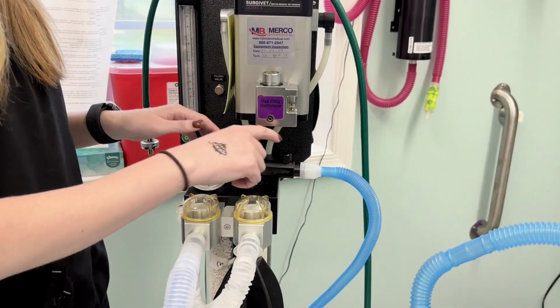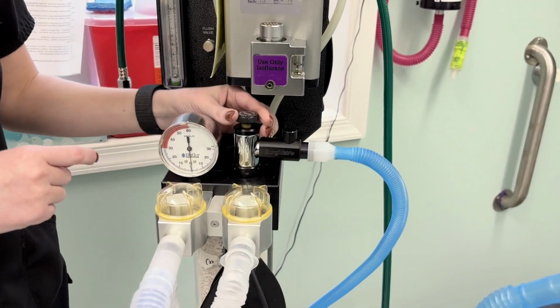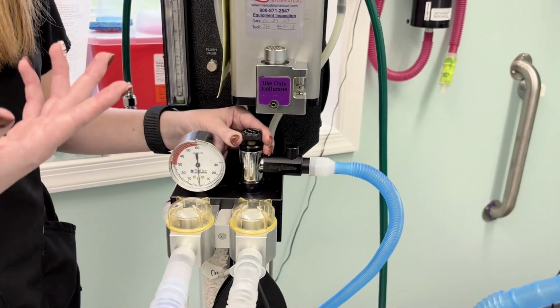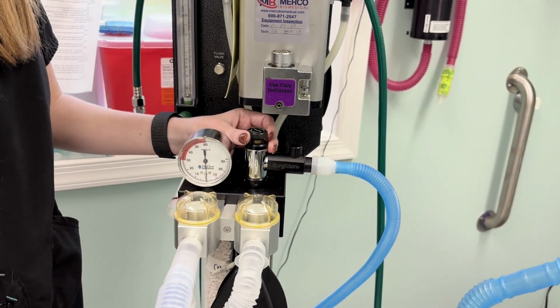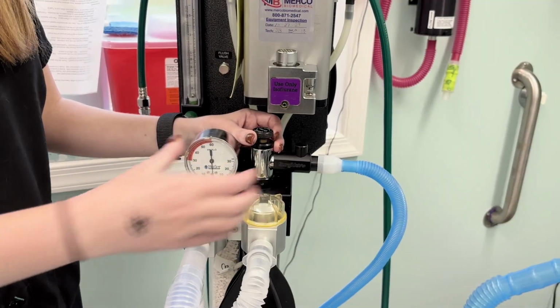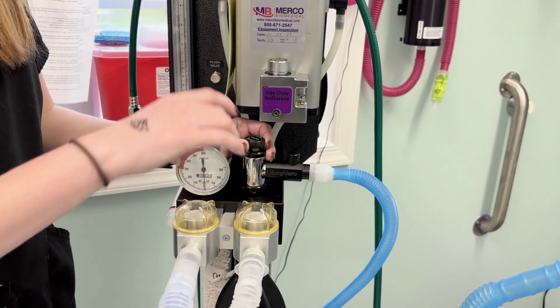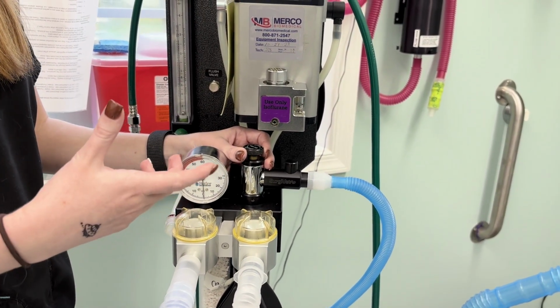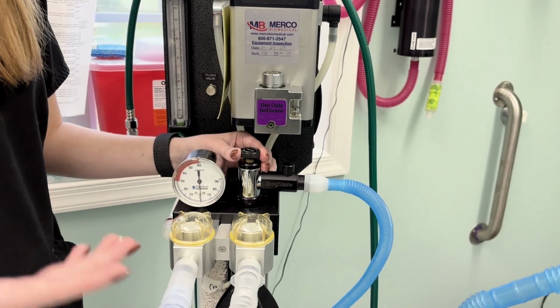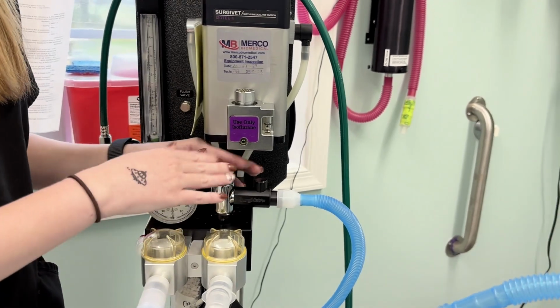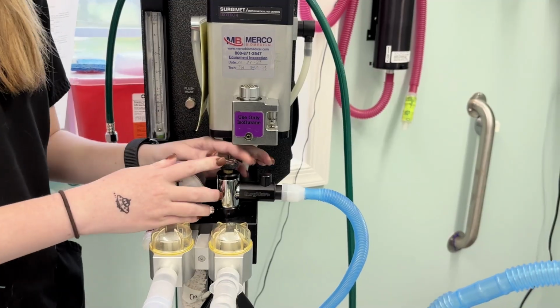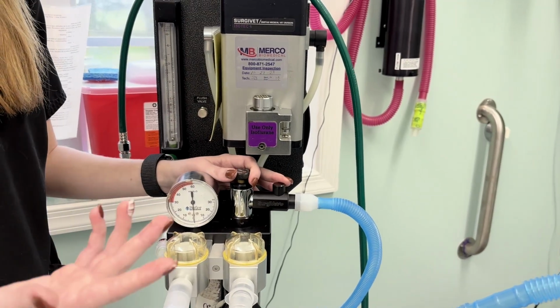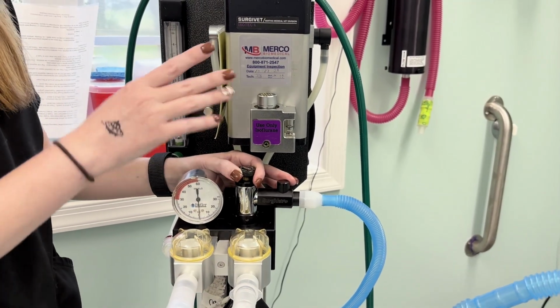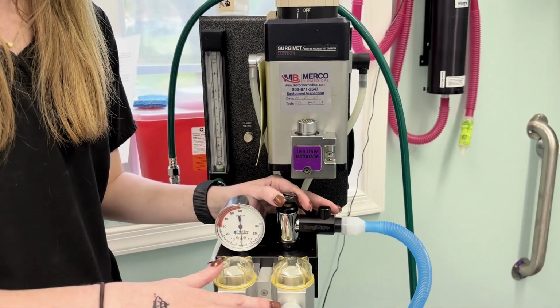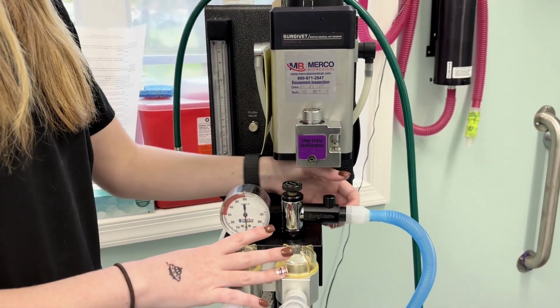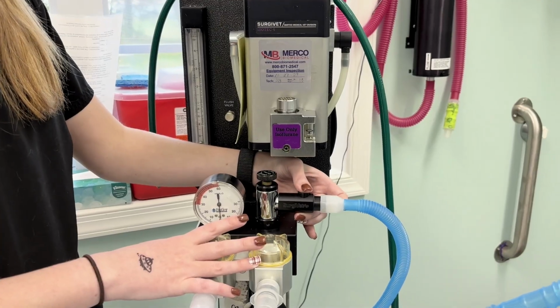And then over here is your pop-off valve. This vents any excess gases, and when you close it, you can give them a breath. It closes off the circuit so that they're not getting anything, and when you open it, they can then take a breath. You always want to make sure this is open during anesthesia, or if it stays closed while the patient is on the circuit and everything's on, the pressure can build up in their lungs and it can be very bad for them.